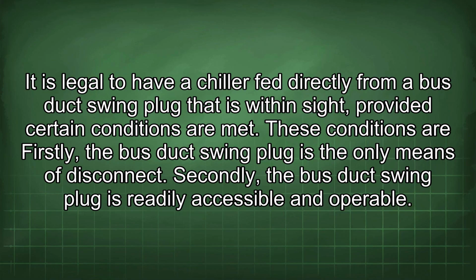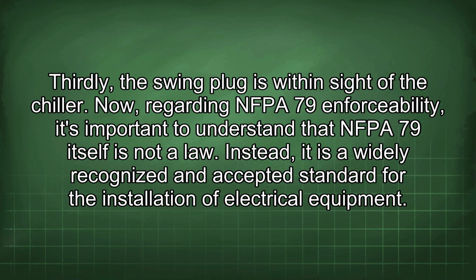It is legal to have a chiller fed directly from a bus duct swing plug that is within sight, provided certain conditions are met. These conditions are: firstly, the bus duct swing plug is the only means of disconnect. Secondly, the bus duct swing plug is readily accessible and operable. Thirdly, the swing plug is within sight of the chiller.